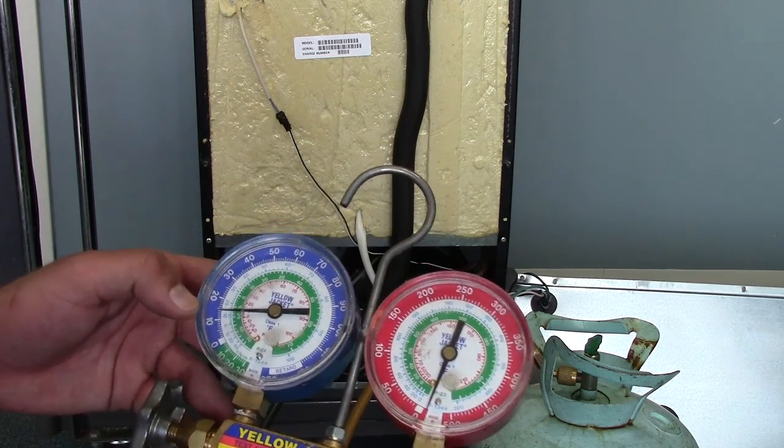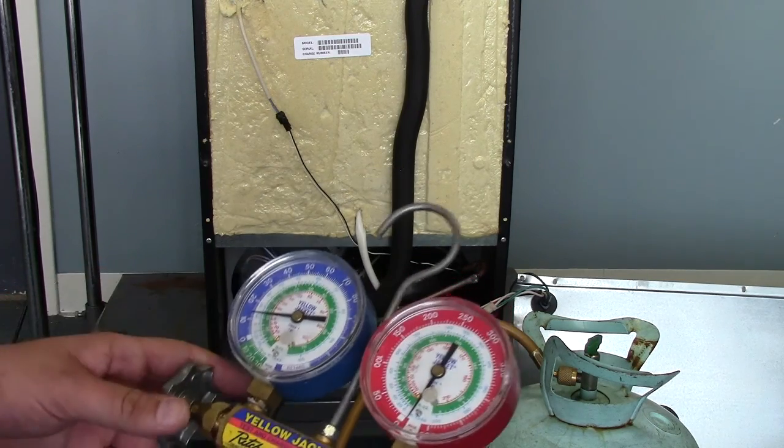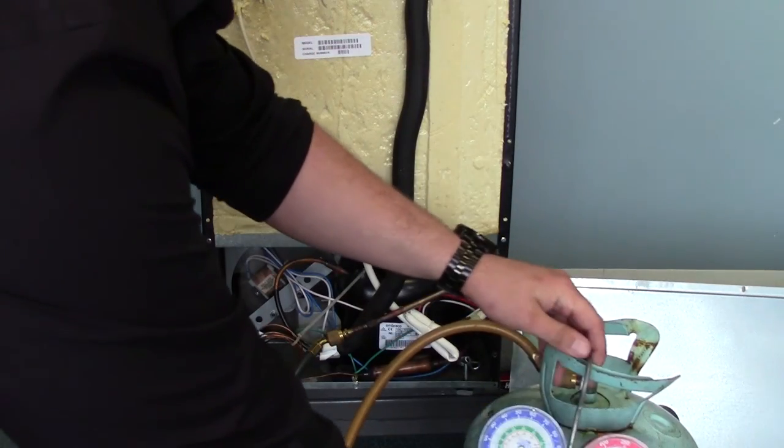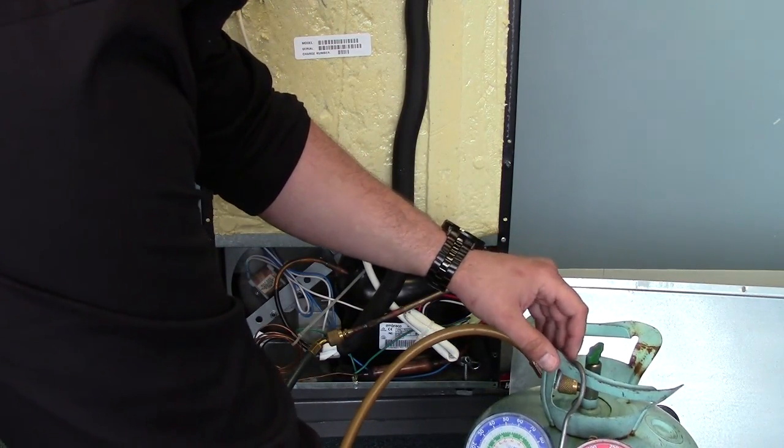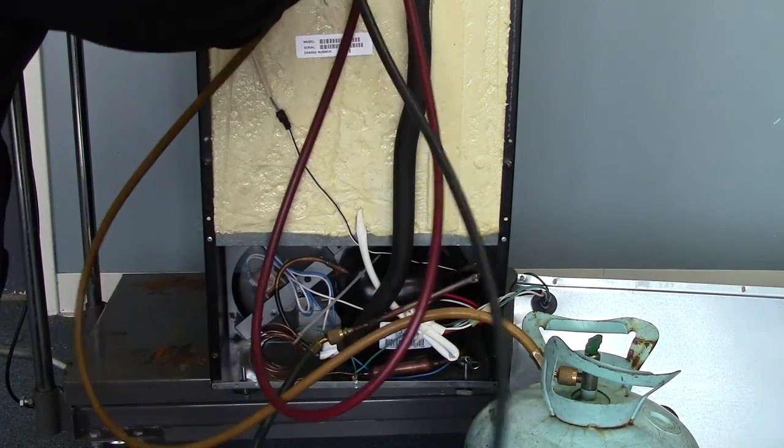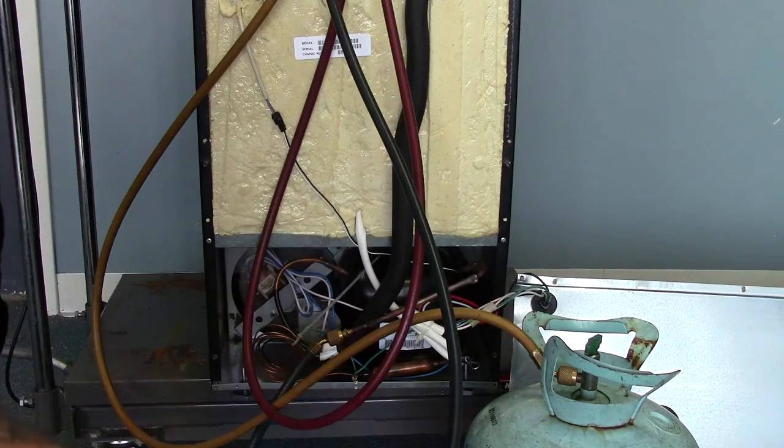Right now it's sitting at about 14 pounds of pressure. It's going to drop a little bit, it's right at 13 now. So what I'm going to do is let that sit there and what we're going to look for is the evaporator, the coils on the inside of the unit to get a good frost pattern going all the way down the back wall.